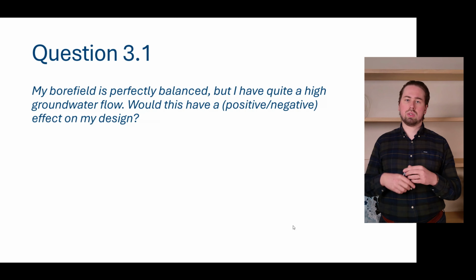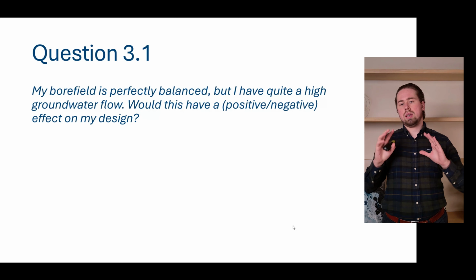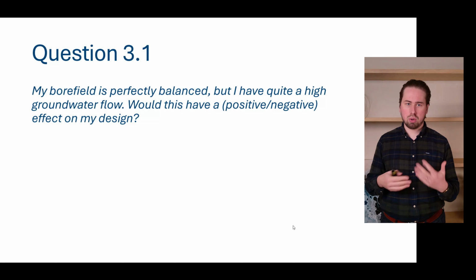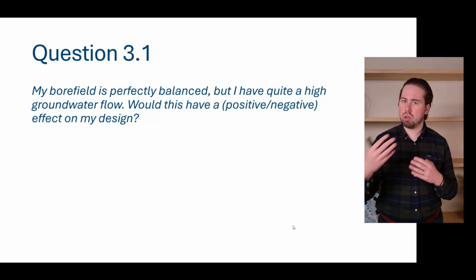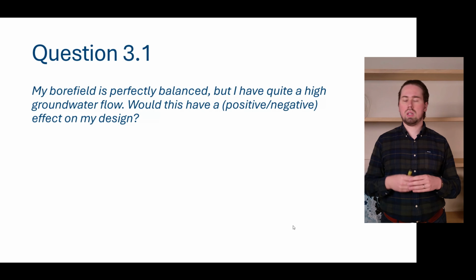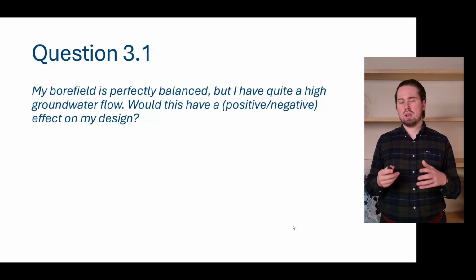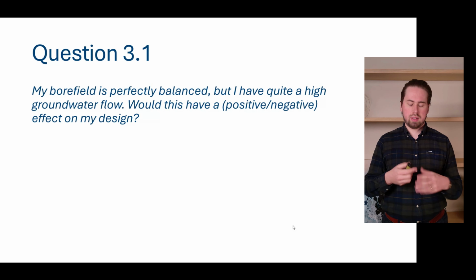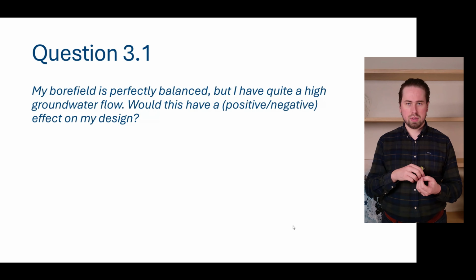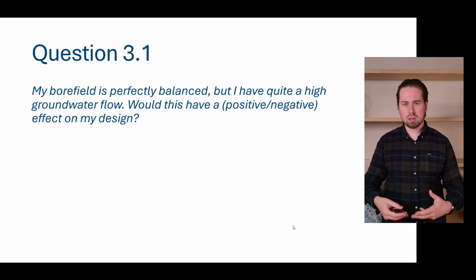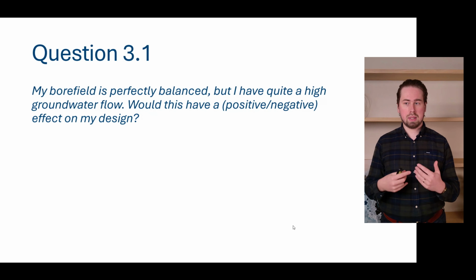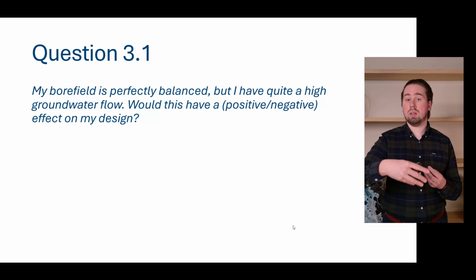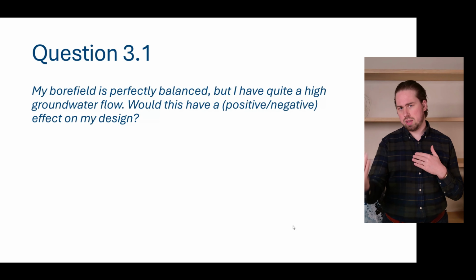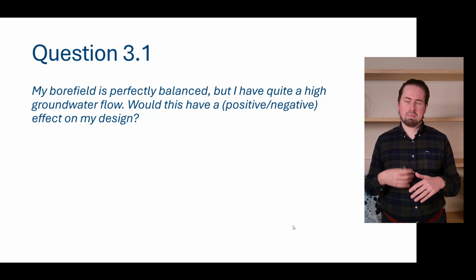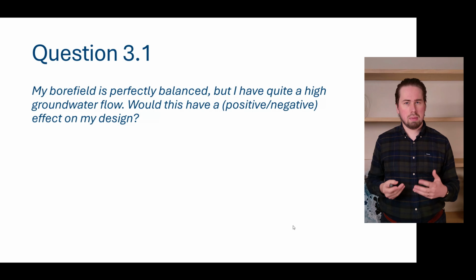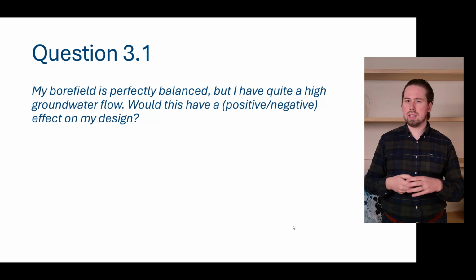3.1 was about the long-term effects of the borehole. So if you say we have a perfectly balanced bore field, so we do not have a long-term temperature drift, and we have a groundwater flow, well, will this have a positive or negative impact? We know that groundwater flows take away part of the energy of your bore field. So if you have an imbalance and your ground cools down year after year, having a groundwater flow is actually really great, because part of your imbalance will be taken away with the groundwater, so to speak. So your temperatures stay more level. But in this case, you might be tempted to say, well, we already are balanced, so it does not matter. But that's not really the case.